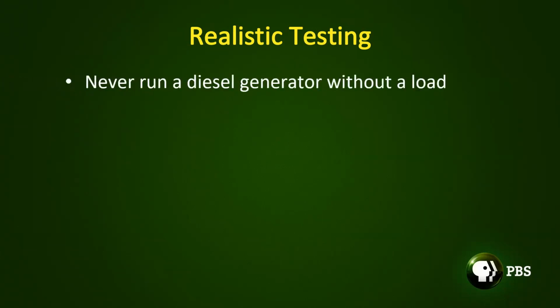That's not a real great idea, because one of my rules is never run a diesel generator without a load. Why? For two reasons. Well, for one, mainly, it causes what's referred to in the industry as wet stacking, which is a polite word for carbon buildup. And the carbon builds up both in the generator, in the cylinders, and also in the exhaust system. And that can choke off an emergency generator fairly quickly.